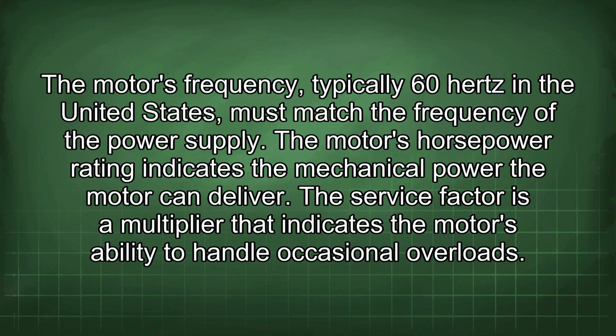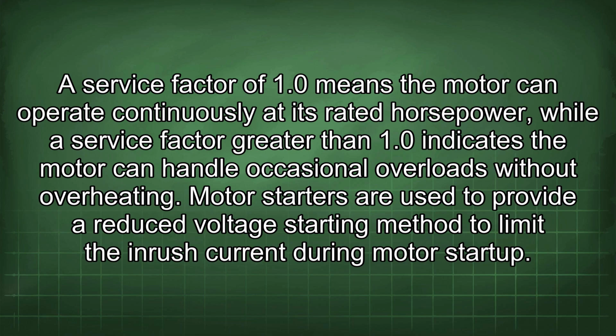The service factor is a multiplier that indicates the motor's ability to handle occasional overloads. A service factor of 1.0 means the motor can operate continuously at its rated horsepower, while a service factor greater than 1.0 indicates the motor can handle occasional overloads without overheating.